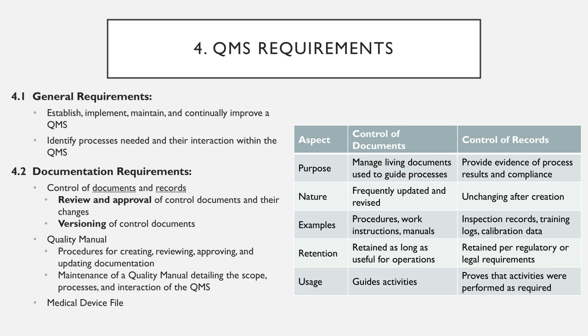So the first document would be version 1, and then you notice a mistake, you make a change, you call that version 2, or maybe you have a different numbering system. You want version 1.1 to show that minor amendment, or it could be a big amendment. And then that second version gets reviewed and approved by anyone with signature authority. And then that next version gets updated as well. So it's not trivial to just make a change to something, and you can't change an original document without documenting that sort of versioning or that update. And then you have to show that that update got approval from anyone within a particular authority.